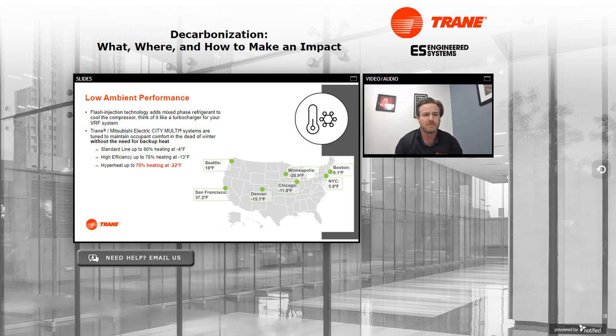So as it stands today, Trane and Mitsubishi City Multi systems, as well as most VRF systems, are tuned to produce that heat at very low temperatures. The map we're showing here is the ASHRAE 5-year data. What this says is for these metro areas, this is as cold as it's been on any given day in the last 5 years. And if you look at our performance charts on the left here, Hyper Heat systems, which is the cold weather version with flash injection technology, really tuned for your cold weather, produce up to 70% heating at minus 22 degrees Fahrenheit. So even in Minneapolis in the past 5 years, you still would have been able to get your heat in the middle of winter. And anecdotally, I haven't heard of any situations in my neck of the woods where somebody has been unable to get their heat in the middle of winter.